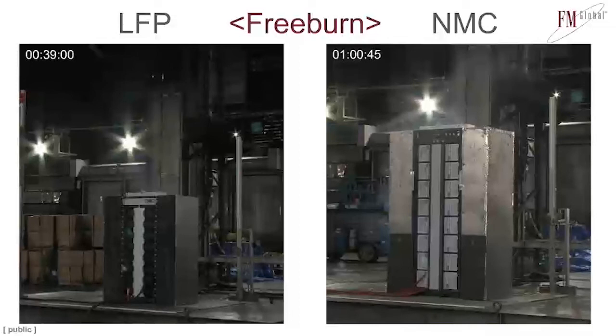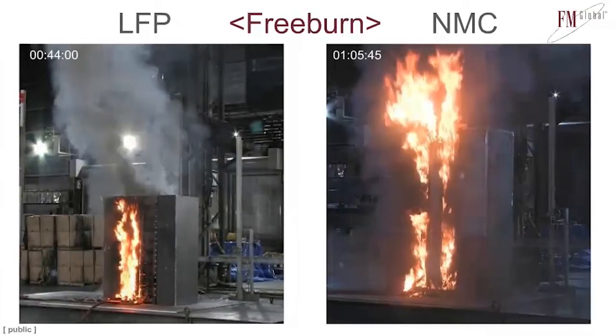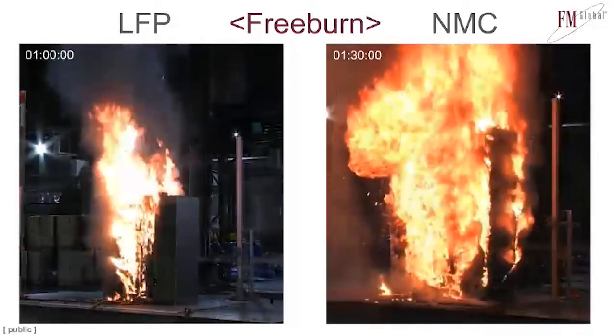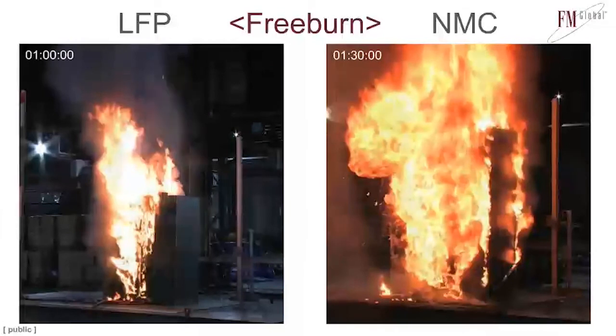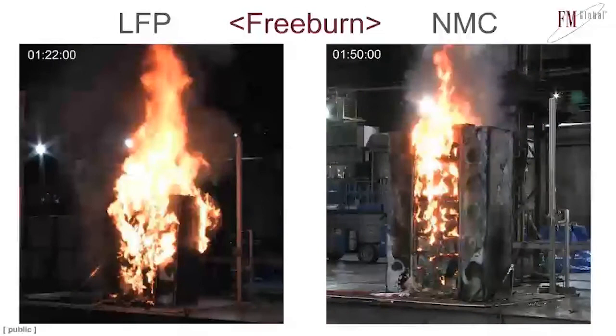You might notice I have some timing up here, and that's related to how the test is conducted. I'll talk about that once we get into one of the videos where I can show you how I did the ignition. But here you can see the fires are face fires, and there's a bit of a difference in perspective of these camera angles. The NMC happens to be a bit closer, but as you see these fires getting large, there is a distinctly larger fire from the NMC. I'll show you some data to show quite how much of a difference it is, but it is a very, very distinct larger fire from the NMC.